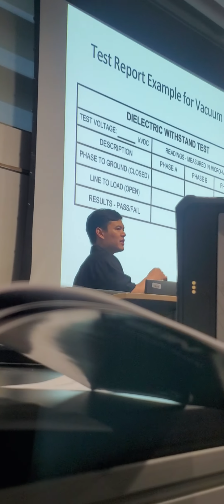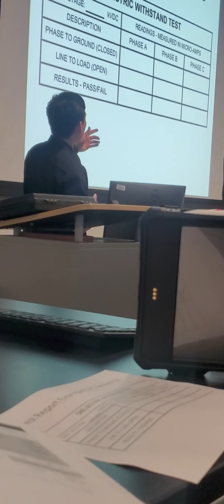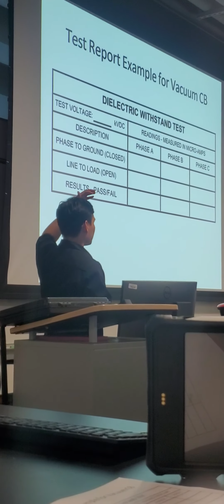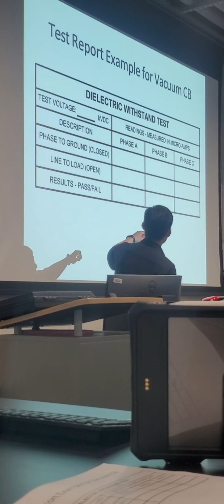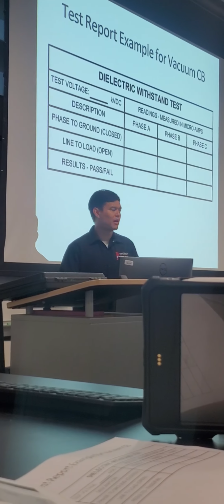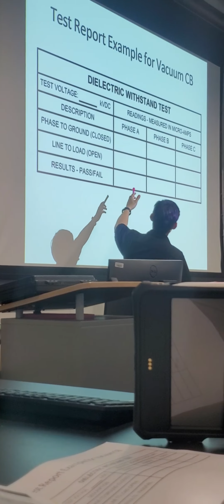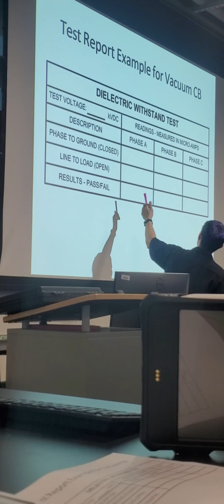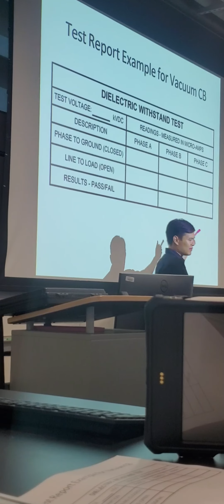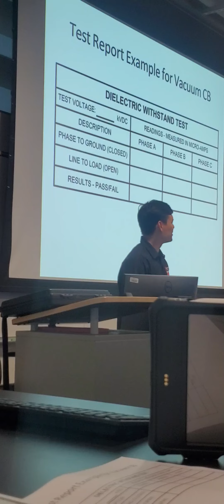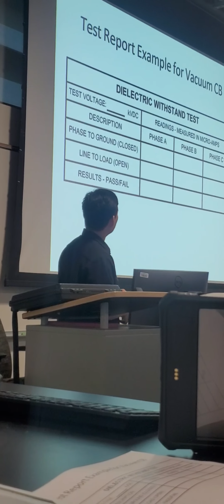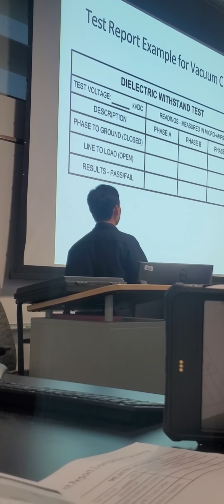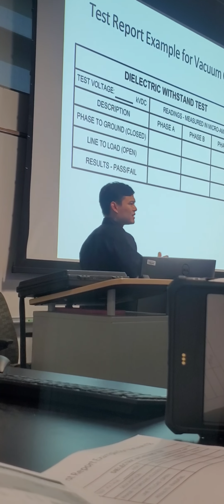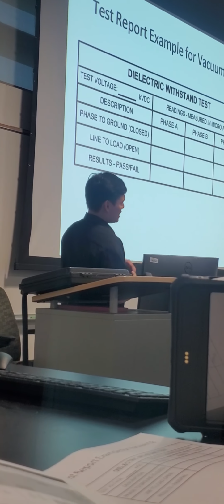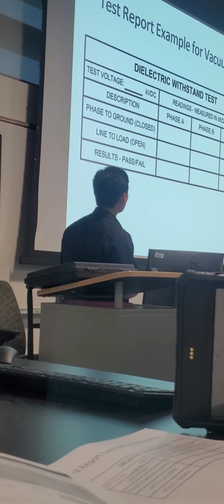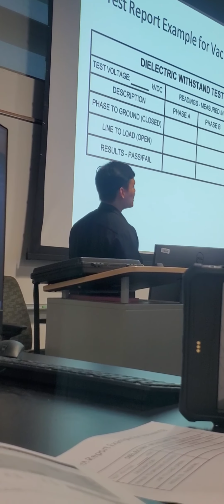Exercise caution if you're entering data digitally, like a lot of companies do, because you can only enter a numeric value, so you wouldn't be able to specify milliamps versus microamps. The problem is if you see 2 or 3 milliamps on one line, then the next line says 2,000, you know that doesn't sound right, or one phase is way off from the others. So make sure you're at least consistent with your units. On handwritten test forms, you can specify if you didn't convert, but as always, best practice is to get very good at unit conversion to avoid mistakes.